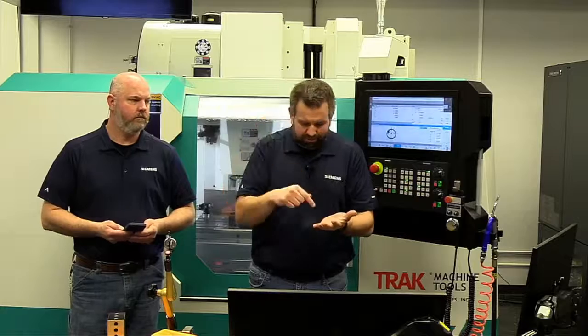And when you indicate that ring in, you're finding the known center of that ring, and therefore you are now going to calibrate off that. So it goes right into measuring. Whatever deviation you have from the center of where your probe was in that ring is the deviation you're going to see every time you see that little bit of kick. So if you don't have that probe center perfectly in the ring gauge when you go to calibrate, that's what that deviation is.